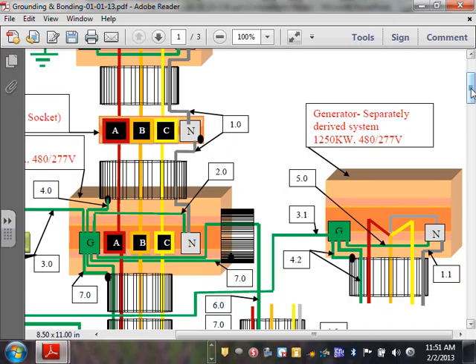and you don't have a separately derived system. You tie the neutral together at that size. And no auto transfer switch. We're having a parallel switchgear, so we do the tying via a parallel switchgear, starting things and closing things through a parallel switchgear. Okay, typically a non-separately derived system. If it's a separately derived system, here's what you do. Number one, does that sound familiar to you guys? We created a neutral. What do you need to do for the neutral in a separately derived system?